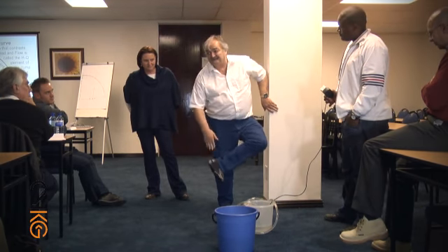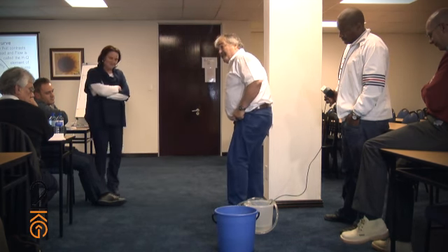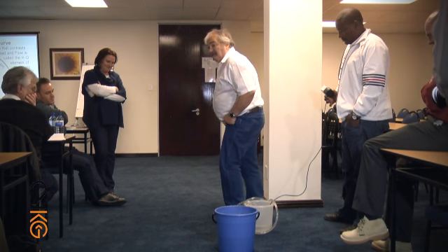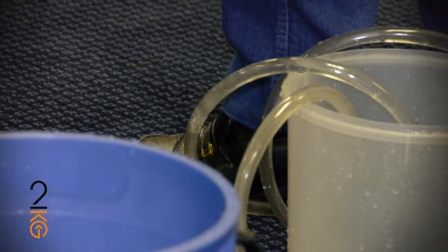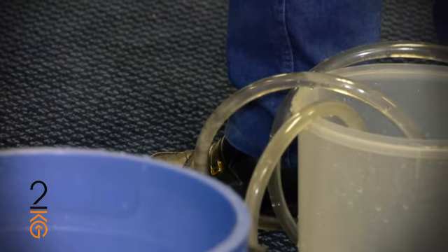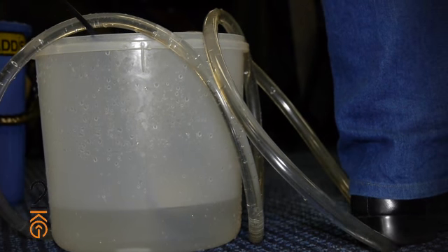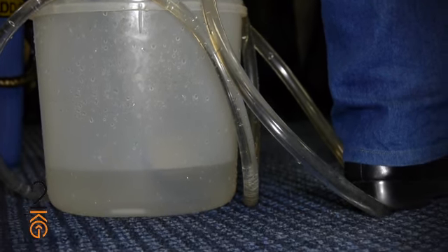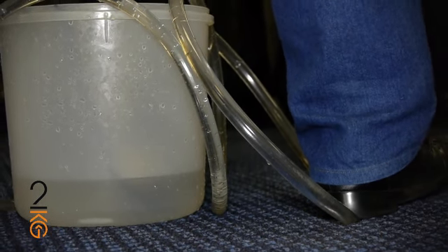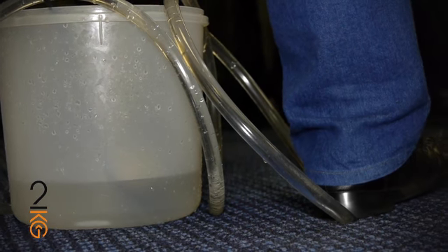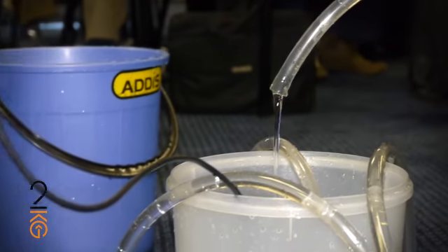This is a valve. I'm just going to step on this pipe right here, put a pinch on this pipe with my foot. So I can either reduce the discharge flow, which means if I reduce the energy leaving the pump, I'm reducing the pump's required energy on the suction side. So I have two options to stop cavitation. I can throttle a valve to restrict the flow leaving the pump, or I can get more energy into the pump.